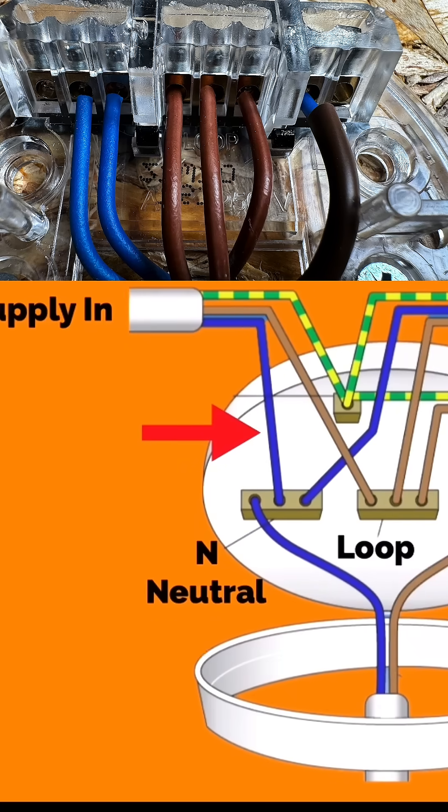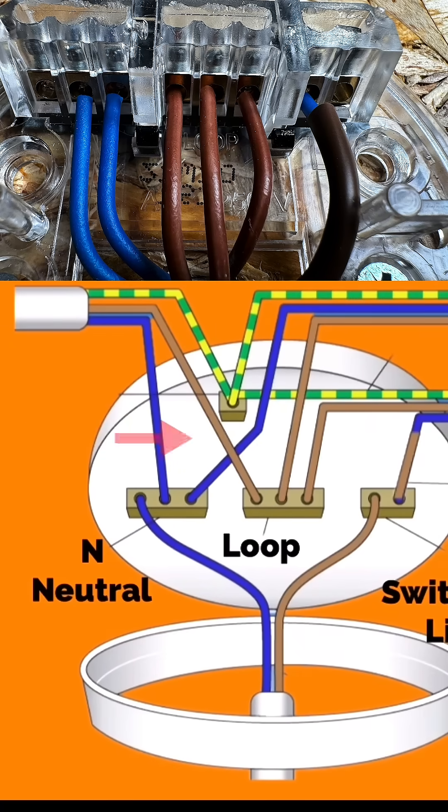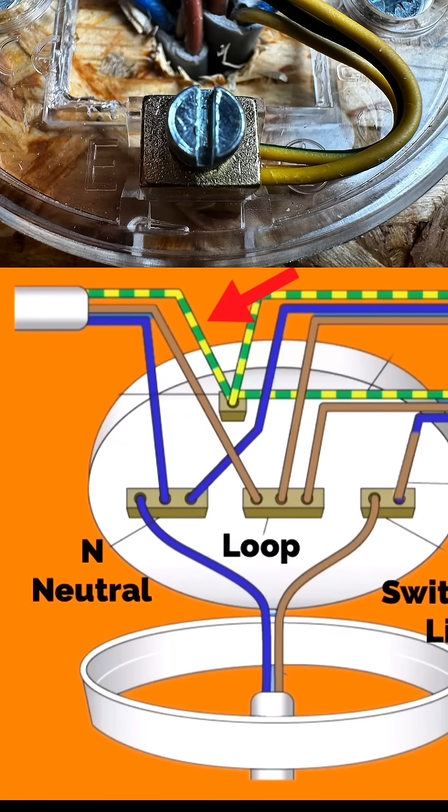It will bring in a permanently connected line, which is connected into the loop terminal in the centre. It will bring in a circuit protective conductor, terminated into the earth connection within the ceiling rose itself.